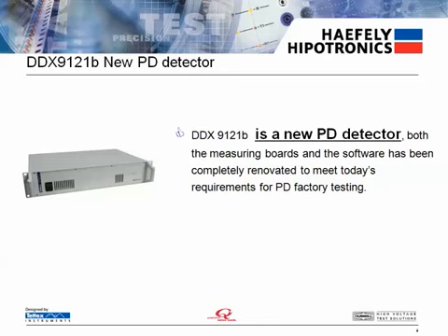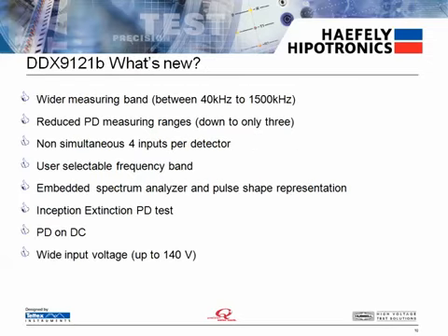The DDX9121B is a brand new detector, not just a modification of previous versions. The measuring boards and software have been completely redesigned to meet today's requirements for PD factory testing. New features and benefits include a wider measuring band, reduced PD measuring ranges, non-simultaneous 4 inputs per detector, a user-selectable frequency band, spectrum analyzer, and pulse shape representation, inception and extinction PD testing, DC PD measurements, and a wide input voltage range.